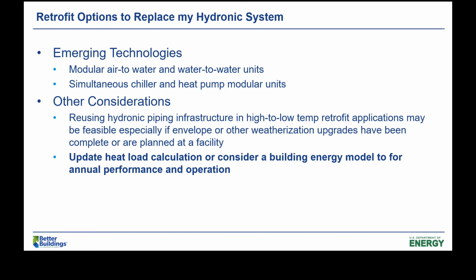Lastly, I'll say this again since it may be the second or third time you've heard it today. Many of our existing buildings had their original heating equipment and heat load calculated at the beginning of the building's original design, before construction. As Paul mentioned with that timeline, buildings inevitably go through many upgrades over their life cycle - a new roof brought up to the current insulation codes of that era, for example - but oftentimes we find that for heating systems, we haven't revisited the sizing.